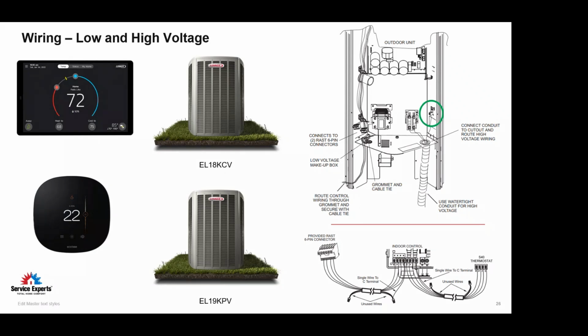Actually, before I get into that, for the variable compressor equipment, wiring is familiar for the high voltage being applied. As you can see, it goes direct to the base of the single pole contactor or 2-pole contactor. But ensure the electrical ground connection has been secured at the outdoor unit before charging with A2Ls. This is not specific to Lennox. This is across the board. In every single one of the manuals I read, this was one of the qualifying notes: ensure that the unit is grounded and properly bonded to electrical ground before charging starts. So please make sure you're doing that.